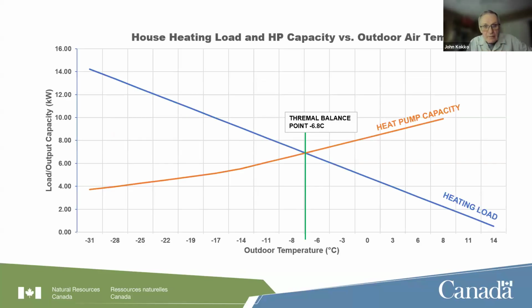So what happens with heat pumps? Well, a house heating load starts from pretty much zero at some higher outdoor temperature, but as it gets colder, the heating load goes up and goes up. This is a Calgary case study, so we're looking at about a minus 31 design temperature, and at that point we're at about 14 kilowatts of heat load on the house.